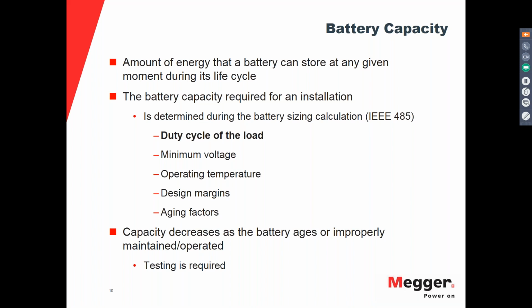This battery capacity is defined during the design process. Whenever the substation or whatever facility the battery is going to be supporting is being designed, the designer collects a group of data to define the capacity that is going to be purchased. Very important in this process is the duty cycle of the load. The designer needs to know how the load is going to behave and how long the battery is expected to support that load in case of a power failure. Also very important is the minimum voltage that the load can work with. These will also define the size of the battery, along with other factors such as the operating temperature, the design margins, and of course, aging factors. All of these define the capacity of the battery that is going to be installed for a facility.